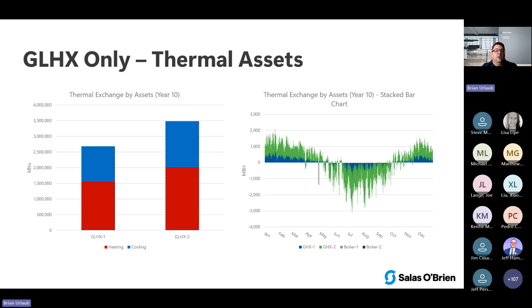We had to put a certain amount of bores in each location and make sure we were optimizing that, but it was difficult because it's a challenging site with utilities and space constraints. So we looked at adding a boiler, reducing the bore field, and putting the boiler in the old steam plant, using it to get enough energy all the way around that loop.